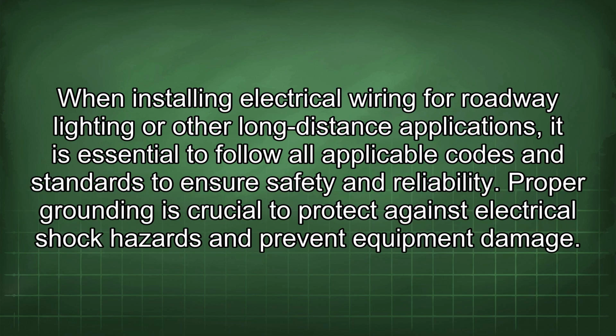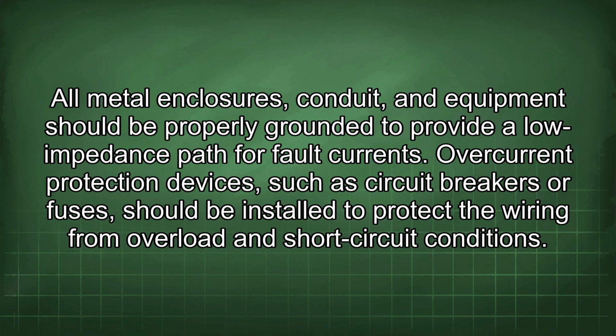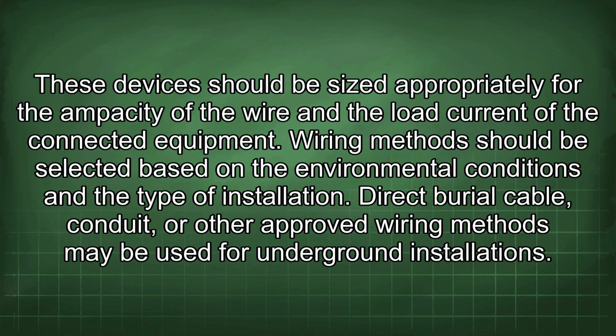When installing electrical wiring for roadway lighting or other long-distance applications, it is essential to follow all applicable codes and standards to ensure safety and reliability. Proper grounding is crucial to protect against electrical shock hazards and prevent equipment damage. All metal enclosures, conduit, and equipment should be properly grounded to provide a low impedance path for fault current. Overcurrent protection devices, such as circuit breakers or fuses, should be installed to protect the wiring from overload and short-circuit conditions. These devices should be sized appropriately for the ampacity of the wire and the load current of the connected equipment. Wiring methods should be selected based on the environmental conditions and the type of installation.